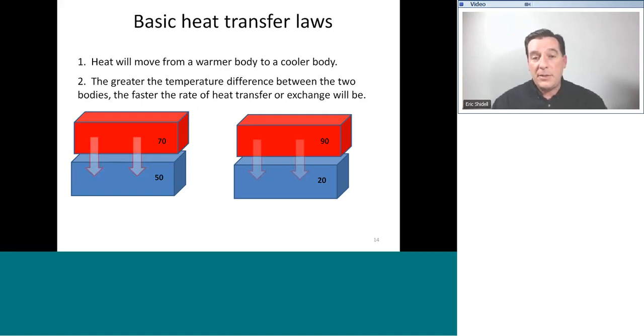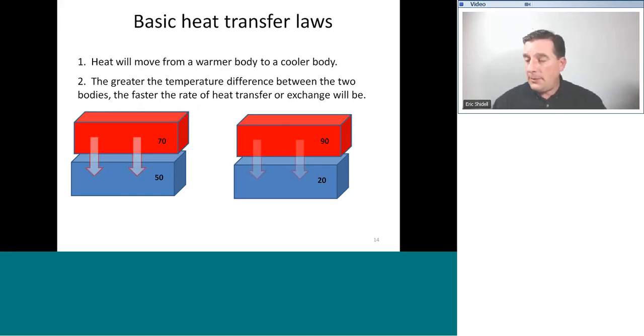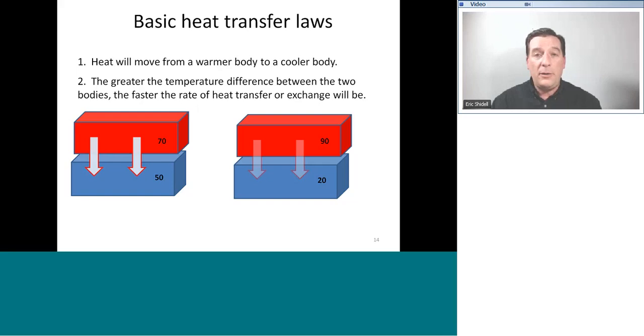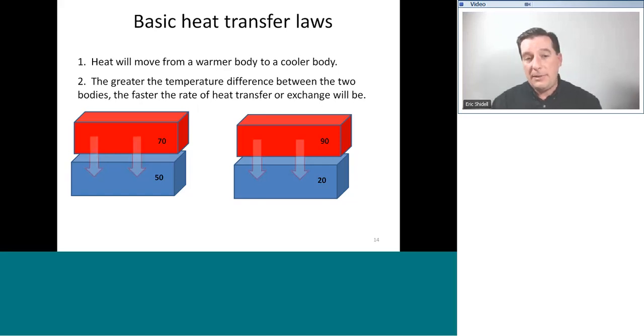This is also the reason why in the wintertime you have a faster rate of heat transfer than you do in the summertime, because there is a greater temperature difference to take into account. That leads back to the earlier question about why a furnace is so much larger in BTU capacity than an air conditioning system. Our furnaces and air conditioners are removing or adding BTU per hour, and the temperature difference in our structure is what determines the heat loss or heat gain in BTU per hour.